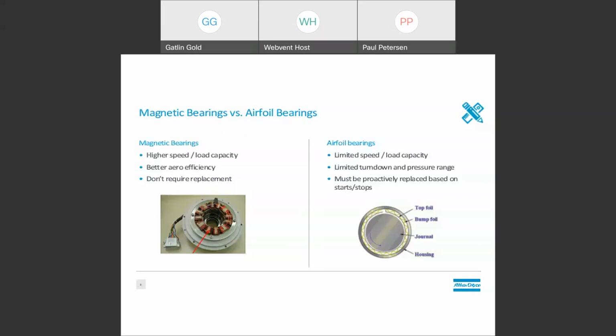Air bearings were introduced by Korean manufacturers in the early 2000s as a lower cost alternative to the magnetic bearing turbos coming from Europe. The limitation of this technology is the number of starts and stops, and that's due to the high-speed contact before and after liftoff. High heat and surge events will deform that thin metal foil we see pictured here. That makes it difficult to create that lift. If the shaft does not lift and the blower gets up to full speed, then you can have a premature failure occur. These machines are designed with the blower and motor as one core. If the bearing fails, then the entire heart of the machine must be replaced. This results in long periods of unplanned downtime with high repair cost.